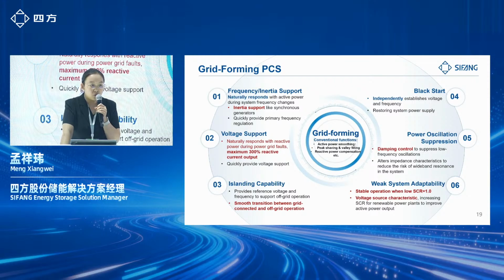For some projects located on an island or in a remote area, the grid is generally weak, and in this condition the grid-forming PCS can provide islanding operation capabilities. For some microgrid applications, it can support seamless transition between grid-connected and off-grid operation. It can also support black start capabilities for the power system. And for a weak system where the SCR is even less than 1, the grid-forming PCS can remain in stable operation and also help increase the SCR for renewable power plants.